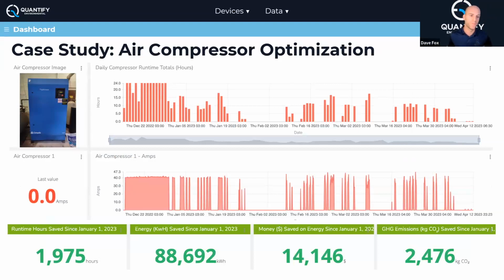We can see on the left here this particular air compressor, and you may be able to relate to this - it's running in a back room where no one ever goes, and it was full out all the time, every minute of every day, even over Christmas and New Year when no one was there, consuming the equivalent of about 30 households of electricity. This is just a 50 horsepower air compressor. We go into facilities with 300 horsepower air compressors, and we're starting to see just how much more amperage draw and cost that is, and a lot of times running unnecessarily.